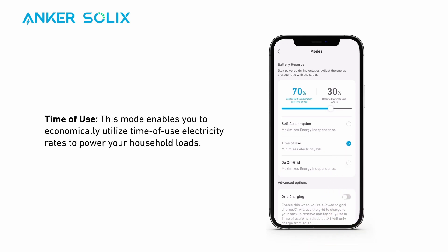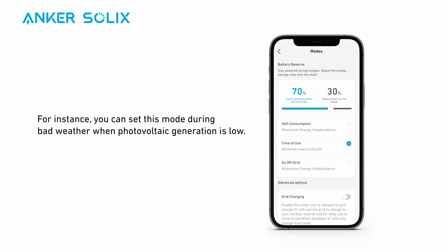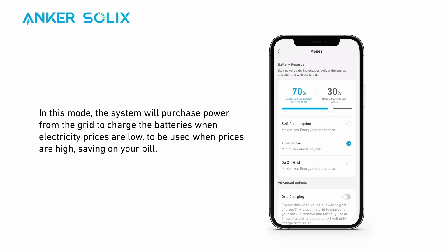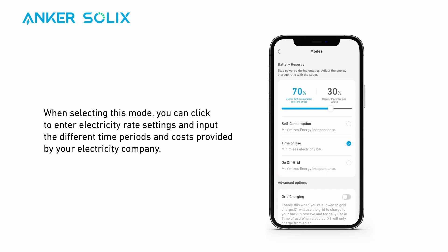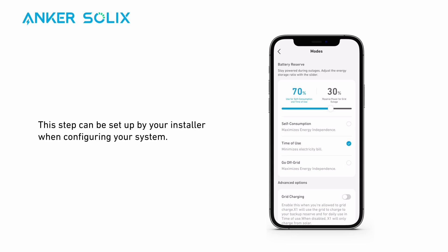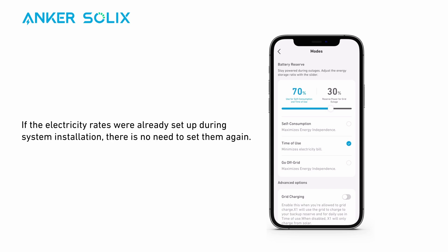Time of use mode enables you to economically utilize time-of-use electricity rates to power your household load. For instance, you can set this mode during bad weather when photovoltaic generation is low. In this mode, the system will purchase power from the grid to charge the batteries when electricity prices are low, to be used when prices are high, saving on your bill. When selecting this mode, you can click to enter electricity rate settings and input the different time periods and costs provided by your electricity company. This step can be set up by your installer when configuring your system. If the electricity rates were already set up during system installation, there is no need to set them again.